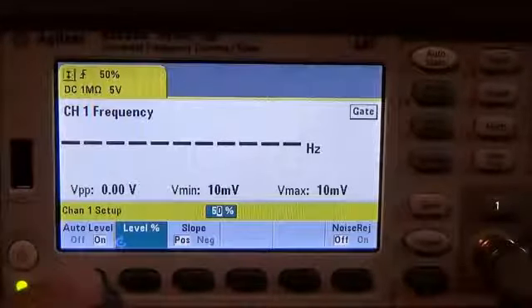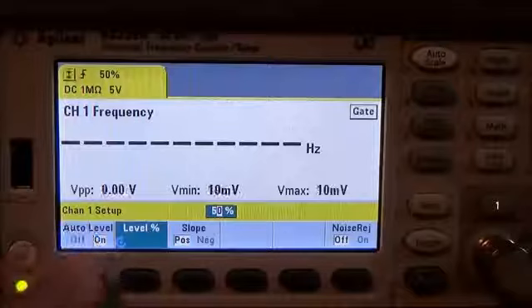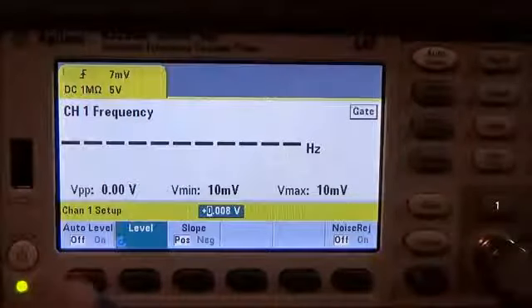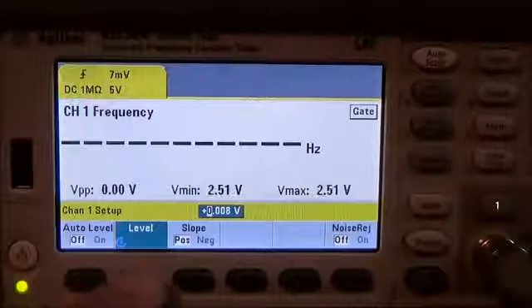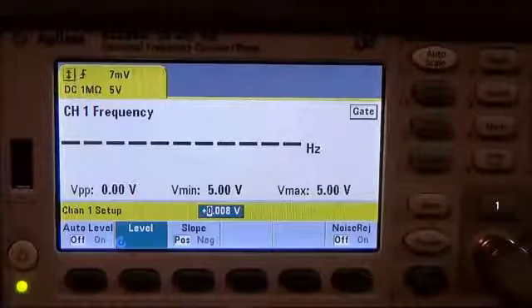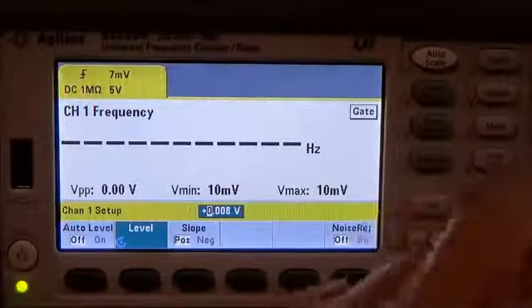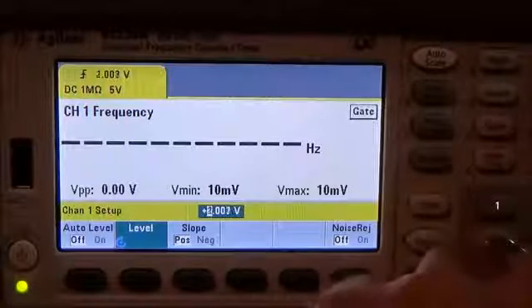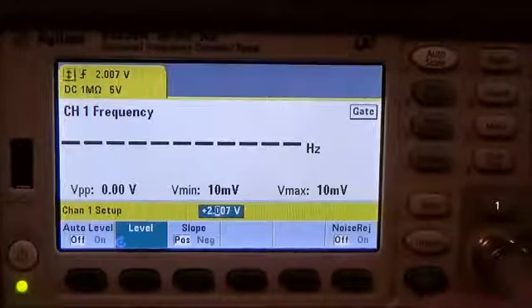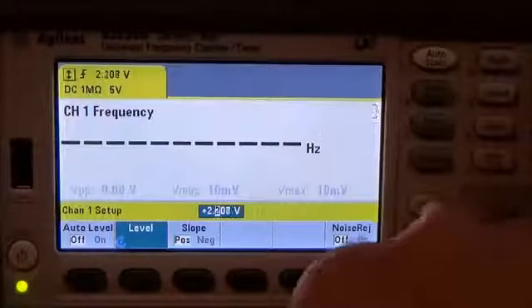So if we press the auto level key it toggles between on and off, and then we can go in and set a level. Since we have a zero to five volt signal we can actually go ahead and increase this to say two and a half volts so we'll be right at the midpoint.